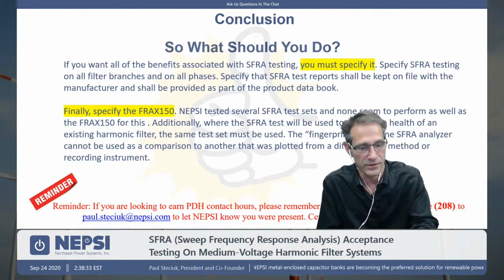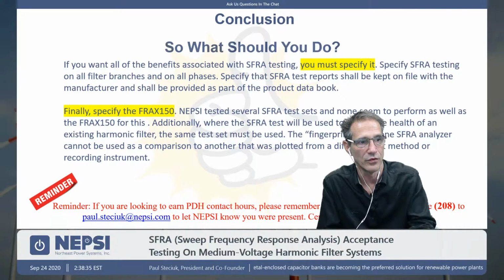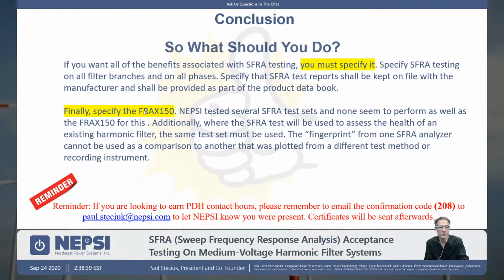And then also specify that you want this Frax 150, the Megger FRAX 150. In the process of evaluating these SFRA test sets, we had a couple of them sent to us. The Frax 150, for the purpose of determining the impedance profile of harmonic filters, was by far the best one. So we would say the Frax 150.